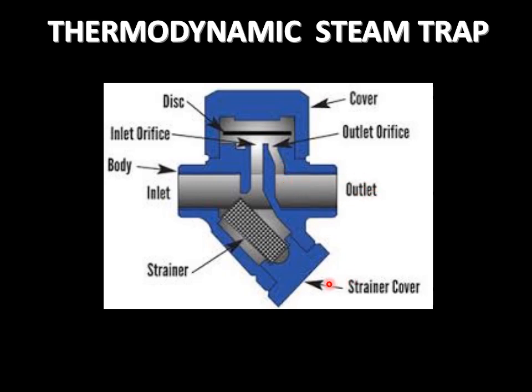Now let us consider the steam condensate enters through this port. Passing through the strainer, it enters the inlet orifice. When there is sufficient condensate, it exerts some pressure on the disk and lifts it up. When this disk is lifted, the condensate from this inlet orifice moves to the outlet orifice and then exits through the outlet port.